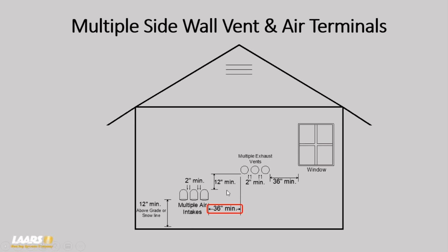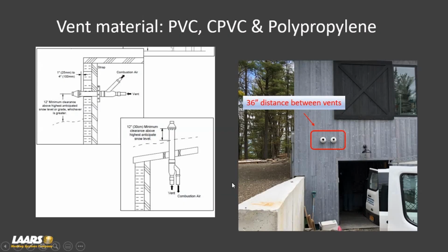12 inches above for your exhaust. Again, this is combustion air, so this is a 90 down, and in that example you might be 15 or 17 inches before you start to recirculate. Keep in mind snow grade, snow level, okay? So multiple units should be 3 feet apart, not only 12 inches apart.